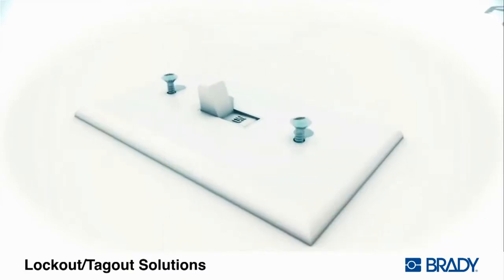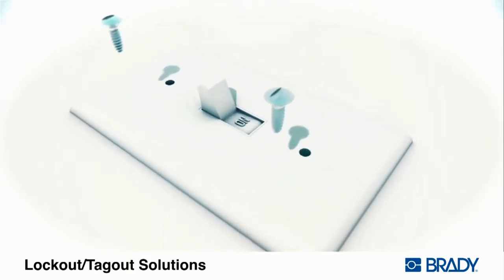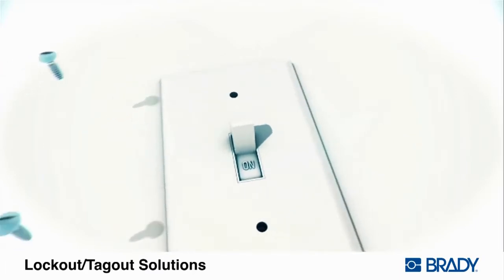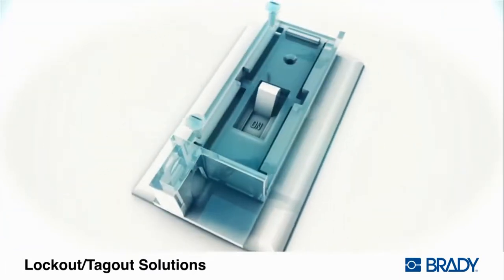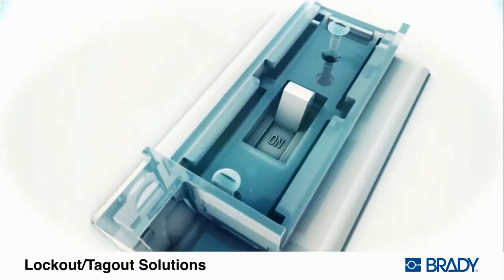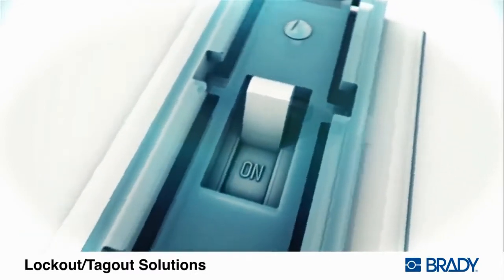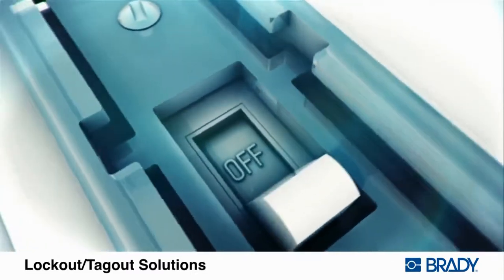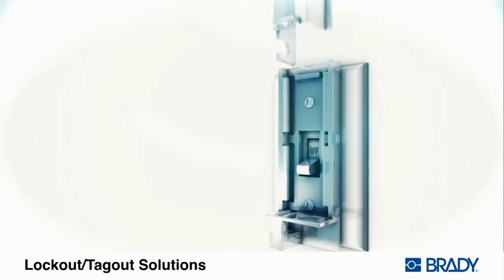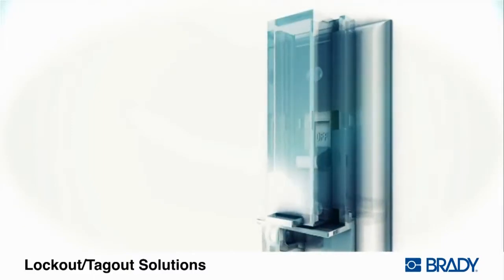To install the wall switch lockout, first remove the wall plate screws. Then, reattach the wall plate along with the lockout device to the switch. Place the switch in the desired position and close the lockout device. Insert the padlock with worker's tag.